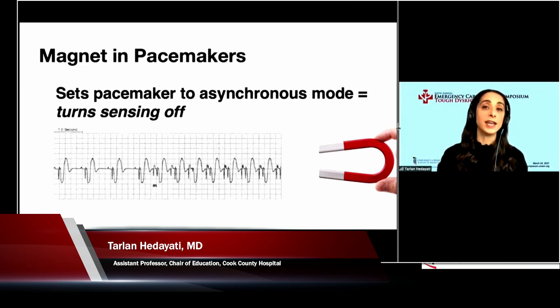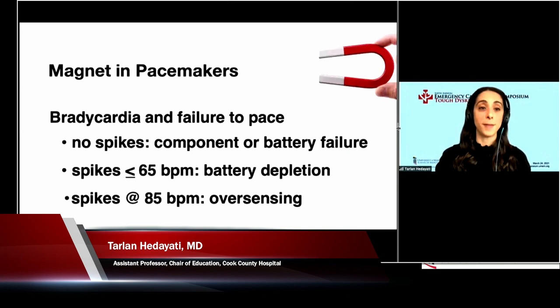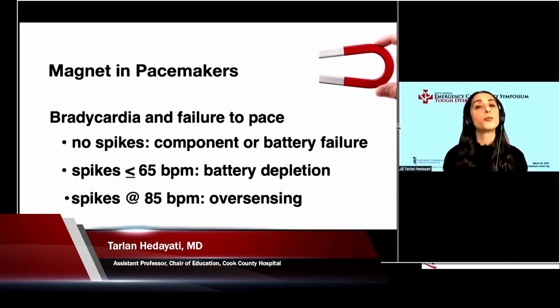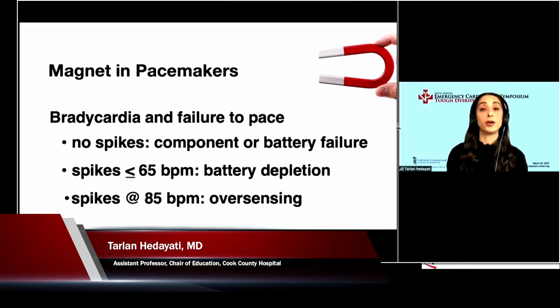Now, if you put that magnet on the device, one of three things is going to happen. Either you're going to get no spikes, meaning the pacemaker doesn't come back online, which indicates the pacemaker is dead—either the battery is dead or there's some problem with one of its components. Now you need to be prepared to externally pace the patient.